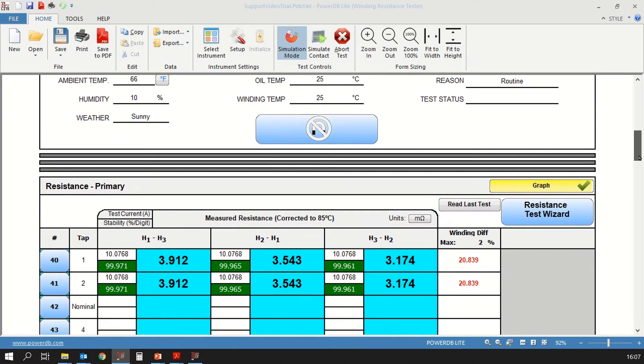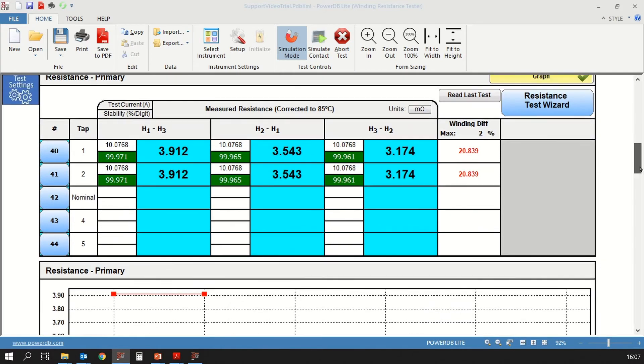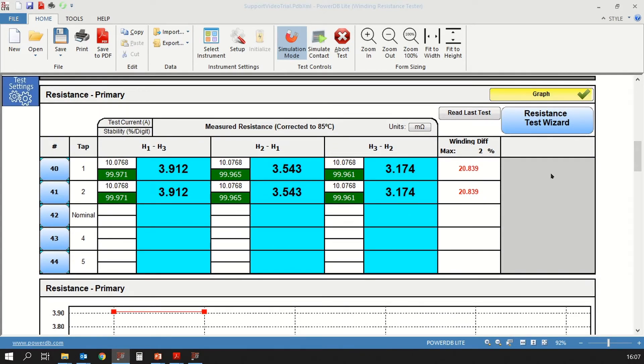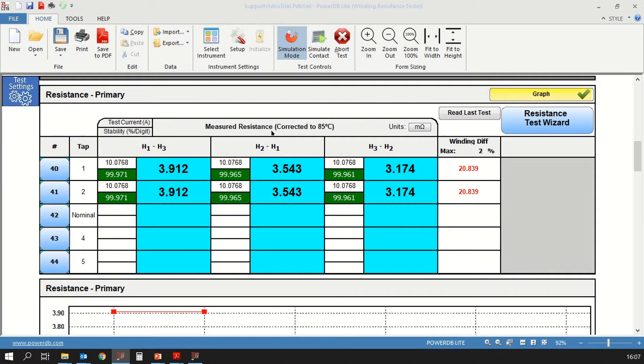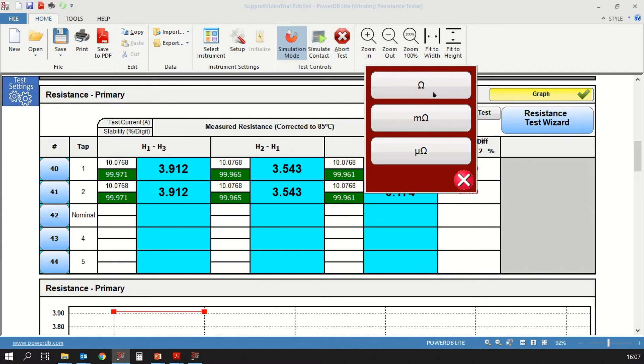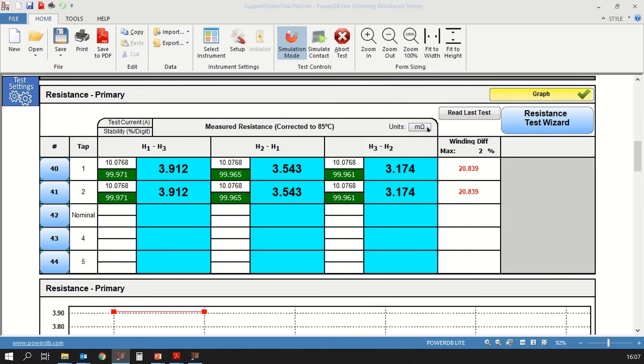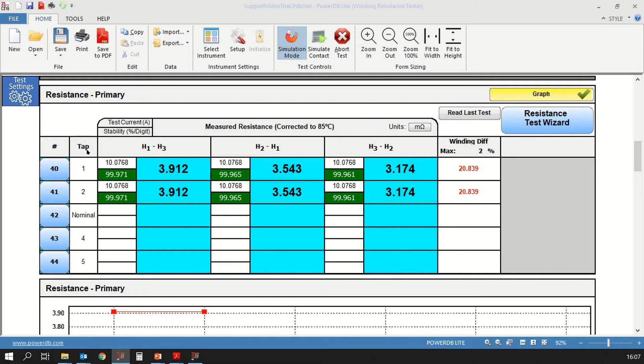Next, we move on to the resistance measurement. Let's look at a few things before we begin the quick test. First, this is the measurement for resistance and this resistance has been selected to be corrected to 85 degrees C. You have the units for resistance. Those are configurable. You can have them in ohms, milliohms or microohms. We are going to select milliohms. In addition to that, you have different line numbers. Here you see 40 through 44, and those correspond to each tap position for this transformer.